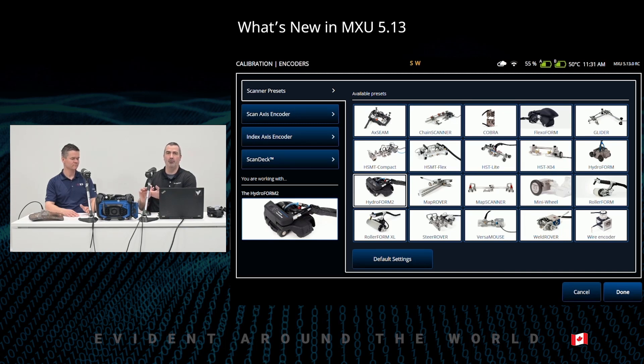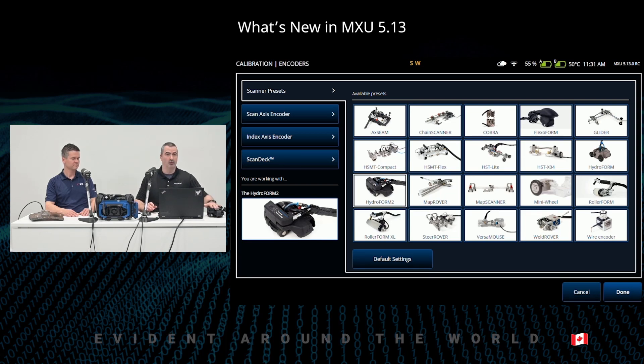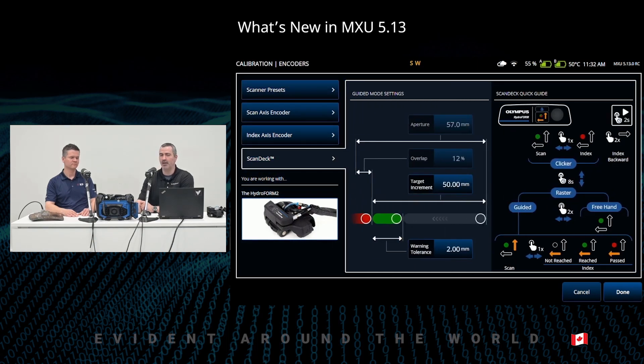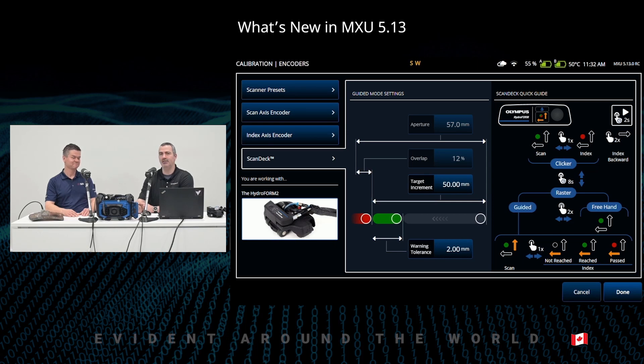Depending on the operation mode you want to use with the Hydroform, you can do one-line scans with clickers, guided clicker lines, or freehand scanning. That can get confusing over time. In the third tab — the scan deck tab — you'll find a cheat sheet for those different operation modes. No need to learn everything by heart. You can refer to this quick guide if you're ever in a situation where you've forgotten the manual at the job site.